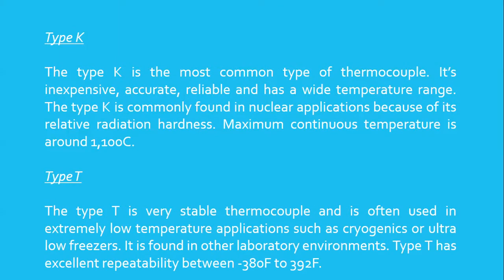Type K. The Type K is the most common type of thermocouple. It's inexpensive, accurate, reliable, and has a wide temperature range. The Type K is commonly found in nuclear applications because of its relative radiation hardness. Maximum continuous temperature is around 1100 degrees Celsius.